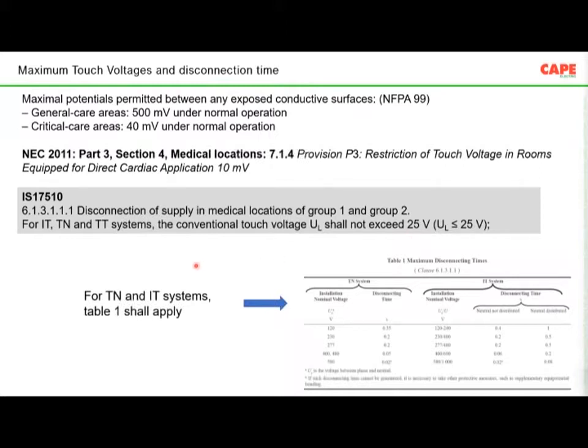Table 1 of the same IS standard says that for general location, we are supposed to use a TN system, and the disconnection times are given. Also for the IT system, the disconnection times are established. If you carefully look into this table, what is missing is the TT system. So we are not supposed to use a TT system in a normal application. TNS is recommended in IS 17510.